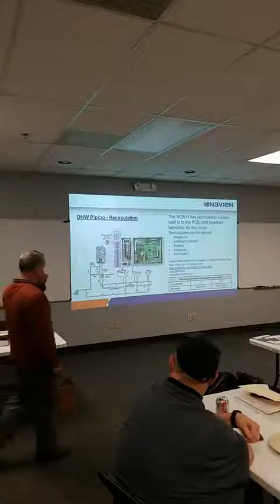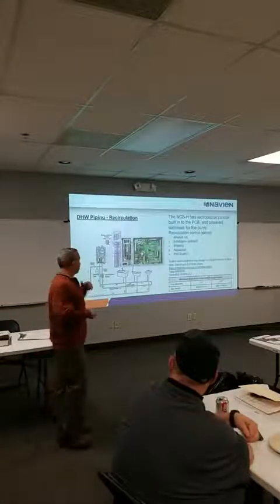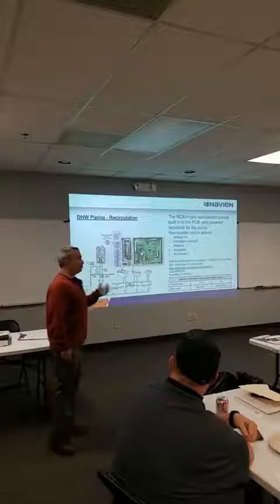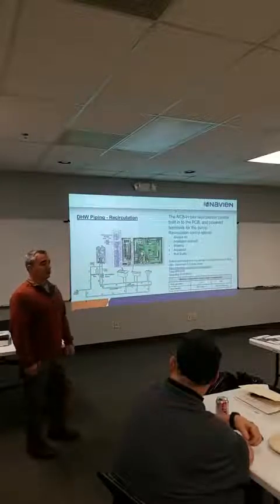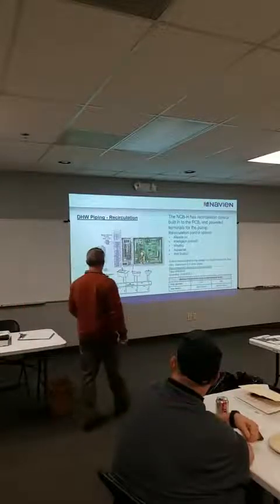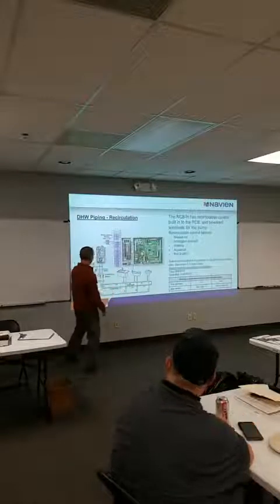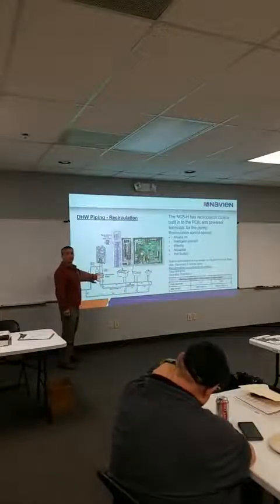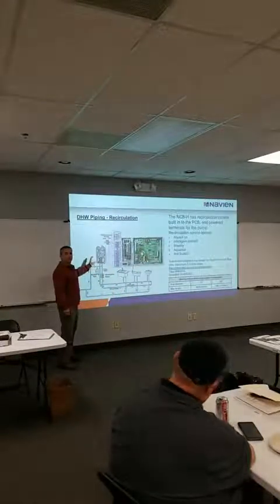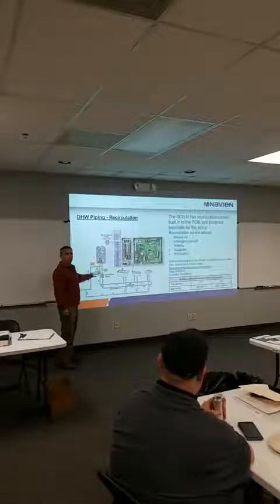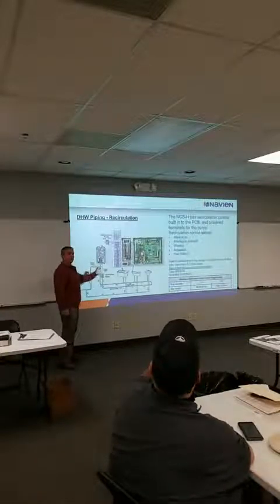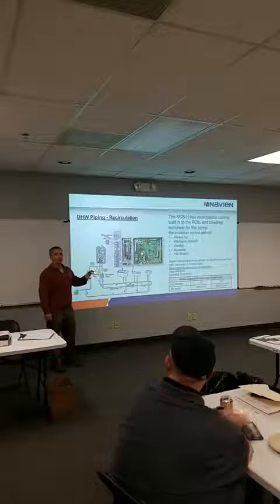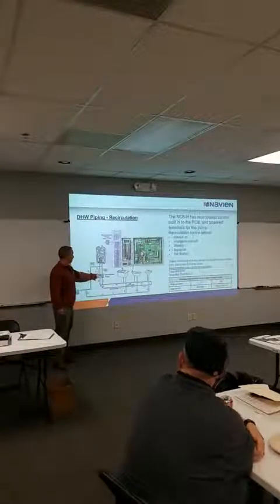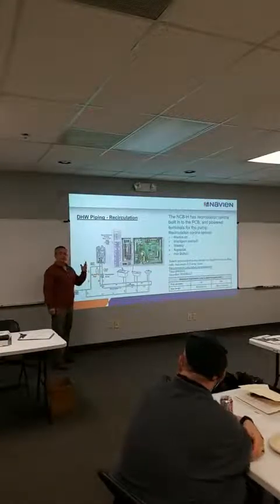So yes, and that's a key point because we always prioritize the domestic hot water in the combi. If this pump was running all the time, you'd never heat your house. Because it locks that 3-way valve. Yeah, it rolls that 3-way valve and goes into domestic mode. So as long as somebody's running a faucet or this pump's running, the heating system is off.